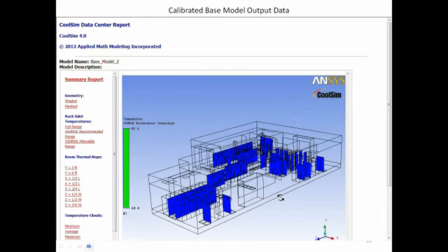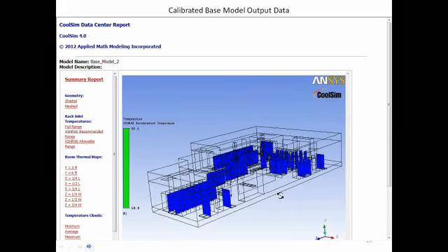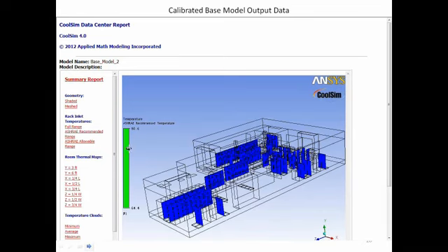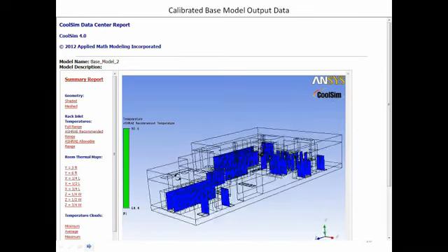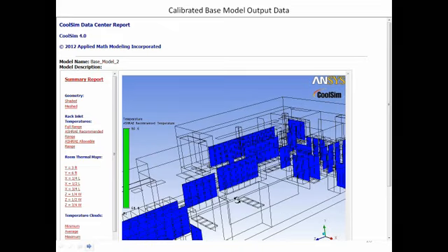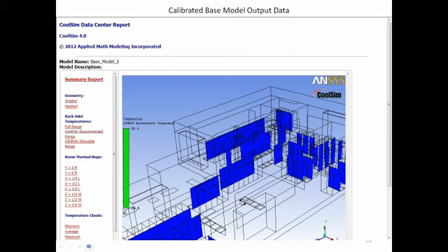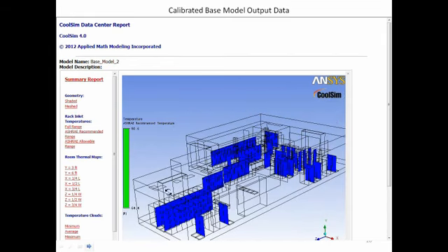So we call this the Visine test, get the red out, you know. But also the blue is too cold. So you can tell in one quick snapshot whether or not your servers are within spec. And you can see here they're not. So the combination of the summary report and this representation here I think are very nice.